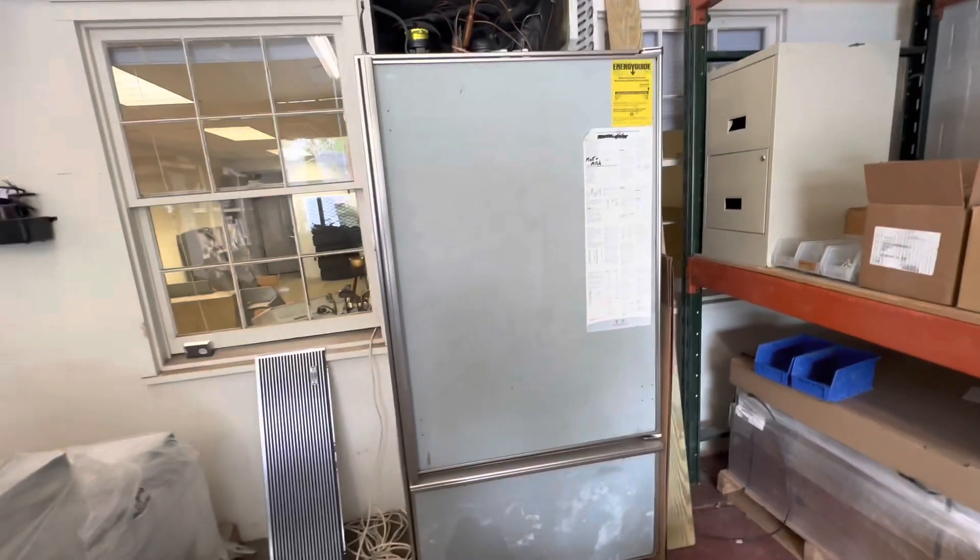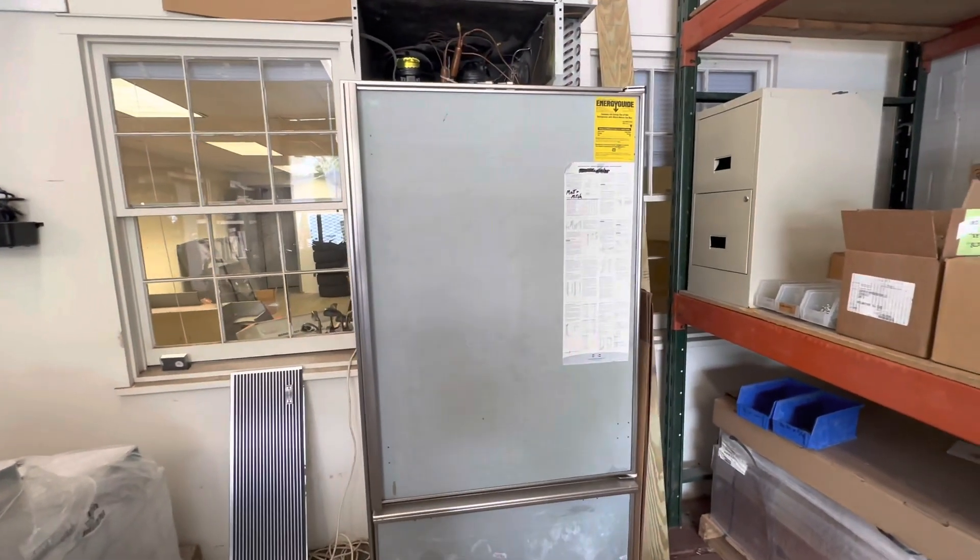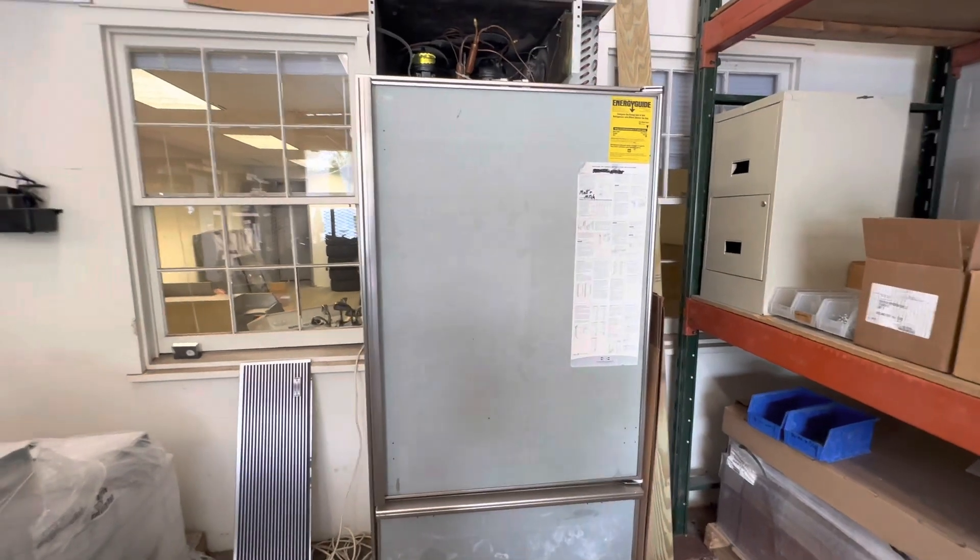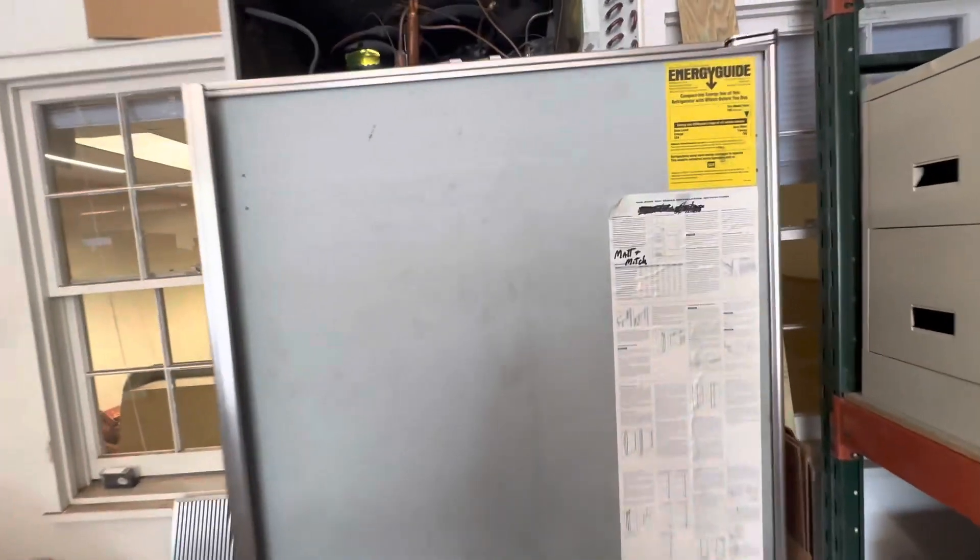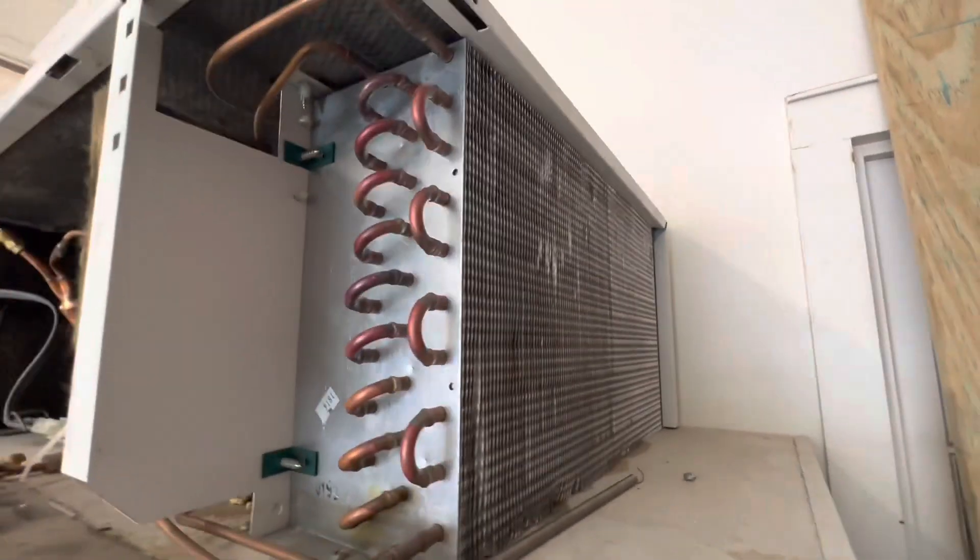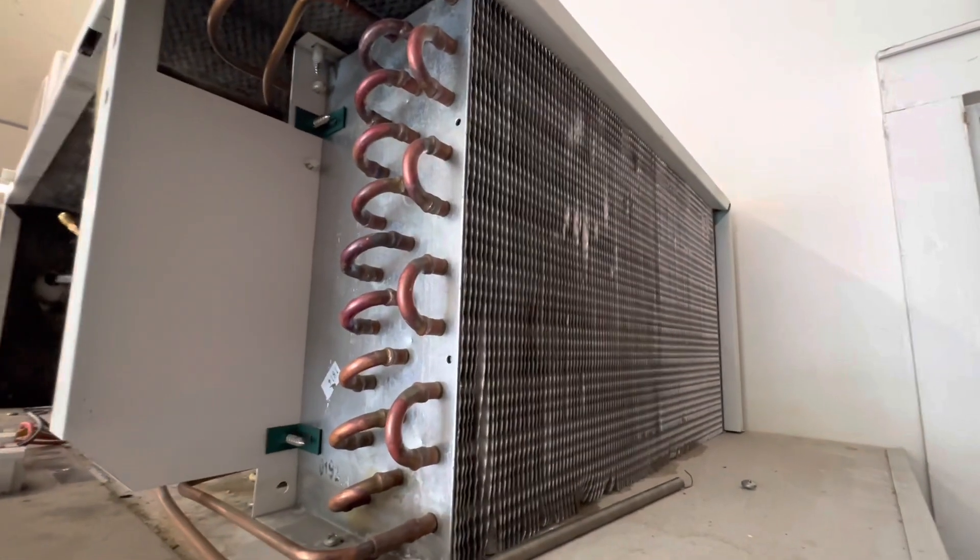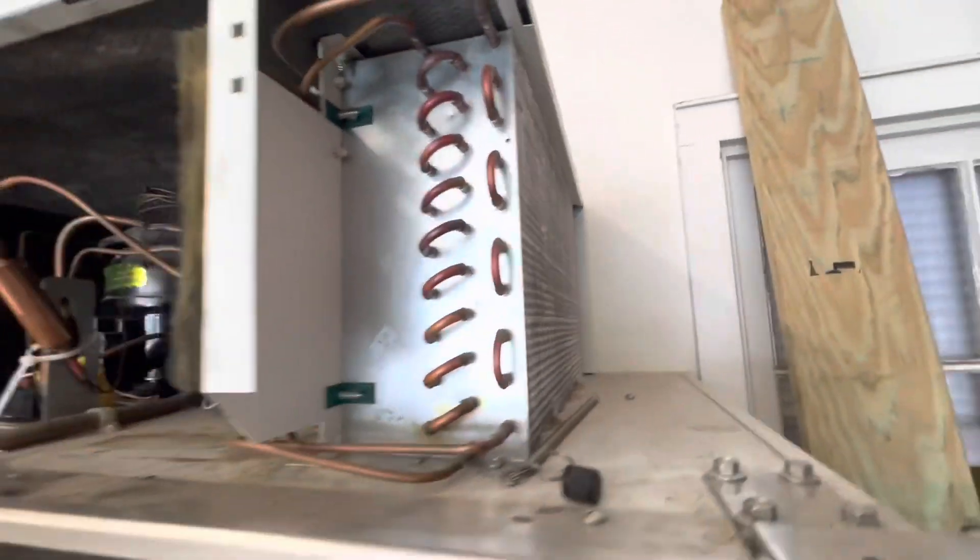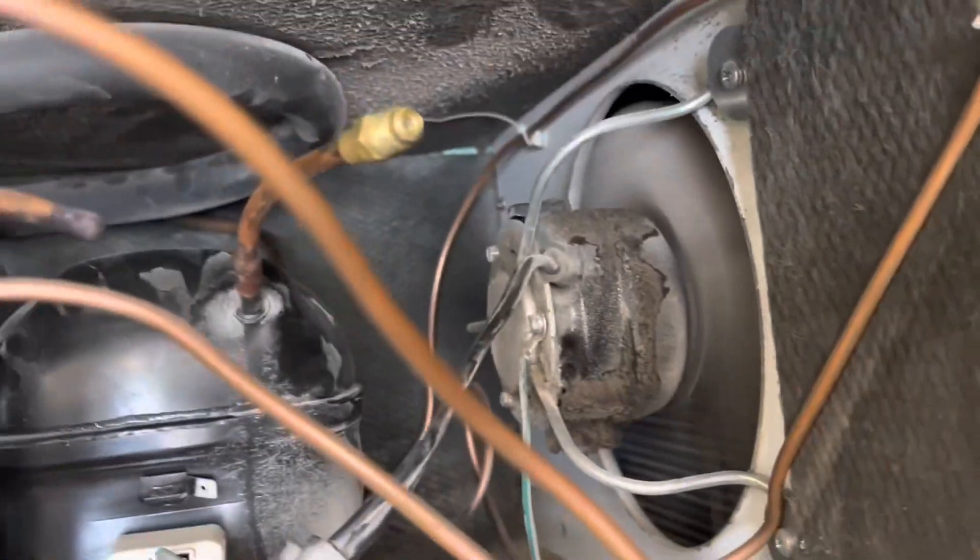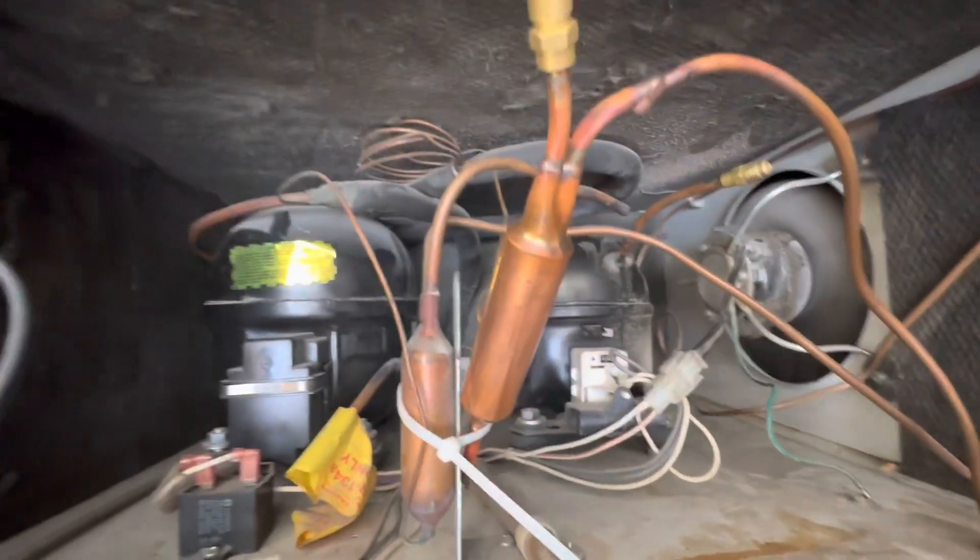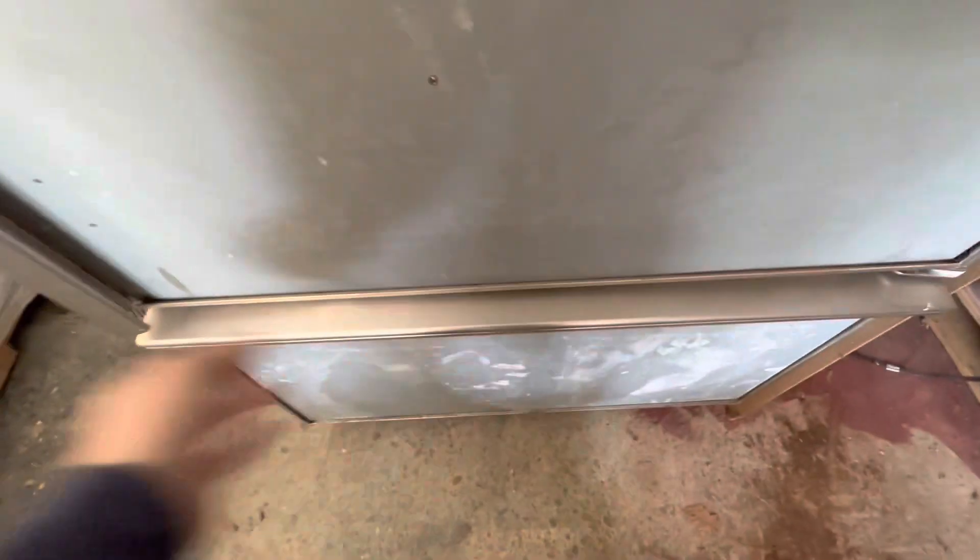Defrost issues can definitely lie in your defrost system. The power your control board sends down to your heaters can be interrupted by your termination switch or your thermostat, but there are other mechanical functions you have to check off the list first. Is your condenser clean? Check. Is your fan spinning up top? Is your condenser fan running correctly and not overheating your compressors, which could prolong run times and cause a frost up?